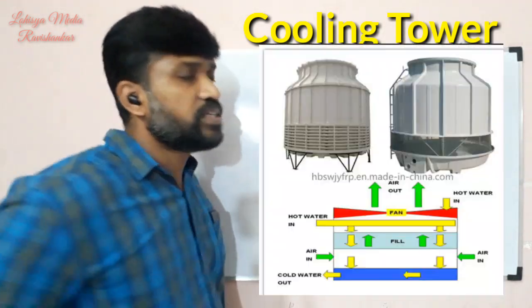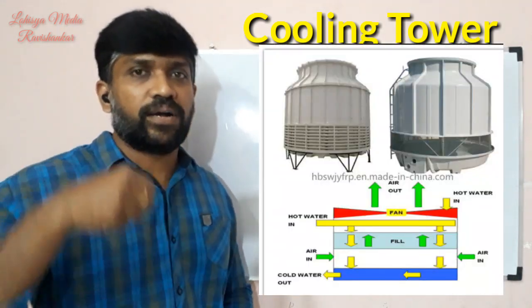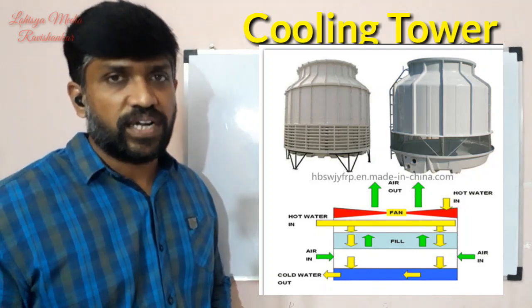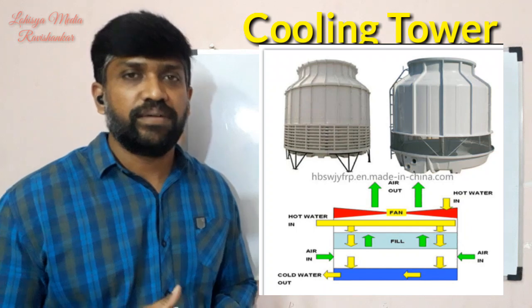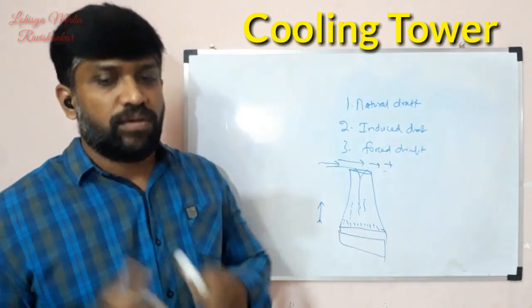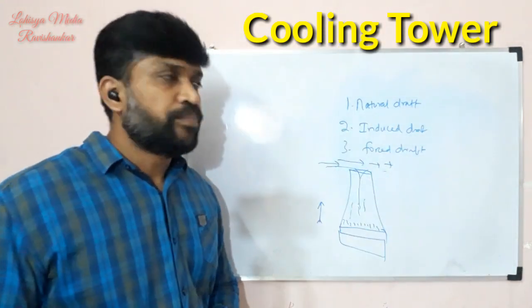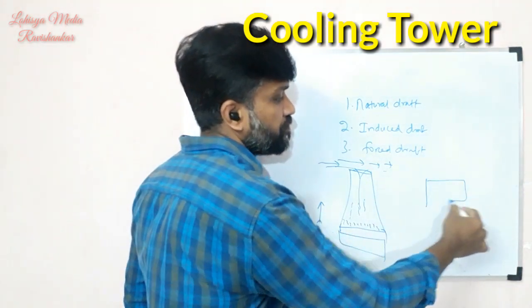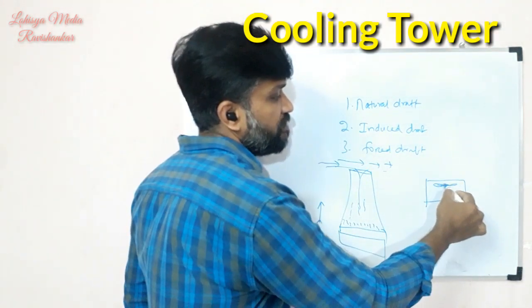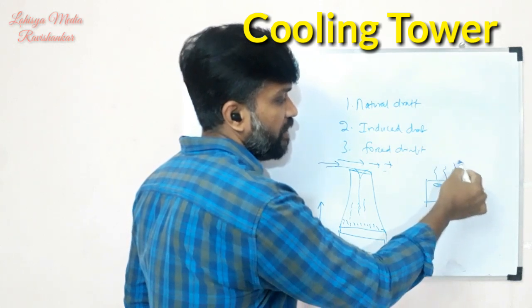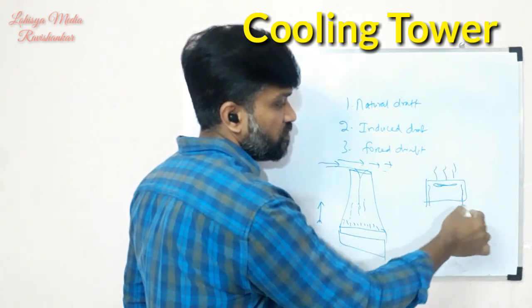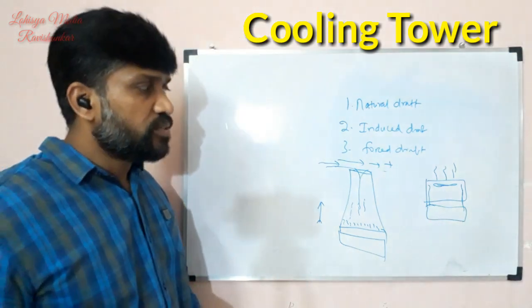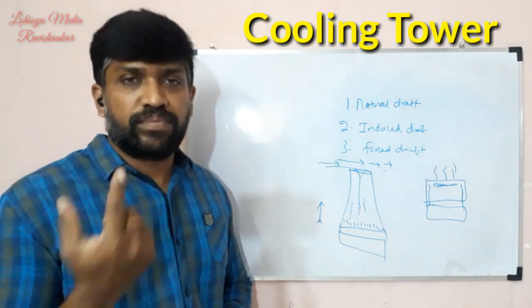Next is induced draft. Induced draft means that air is pulled through the tower. If you have exhaust fans on the top of the tower, that is the induced draft. The fan is placed at the top, and air flows in from the outside. Water flows down inside. Induced draft towers use a pulling fan — the fan is used to pull air through the tower.